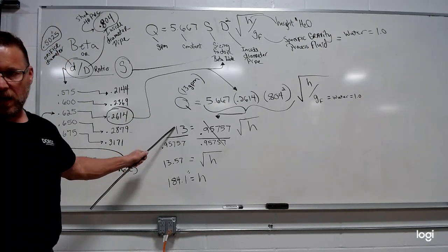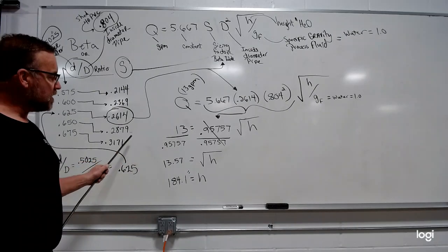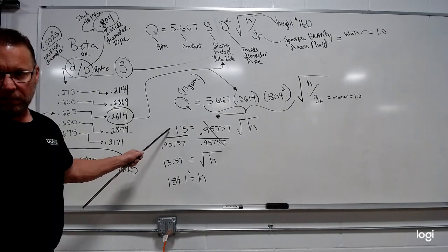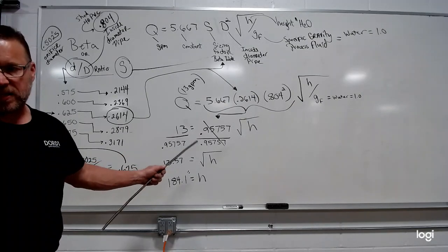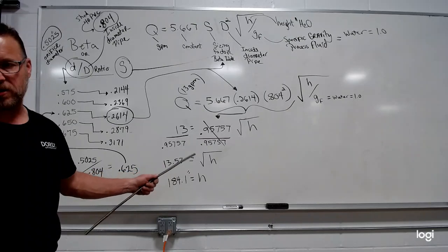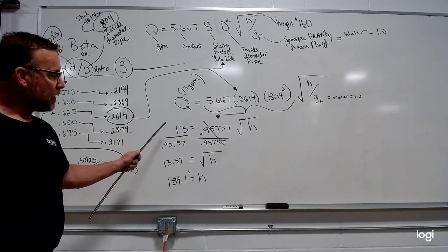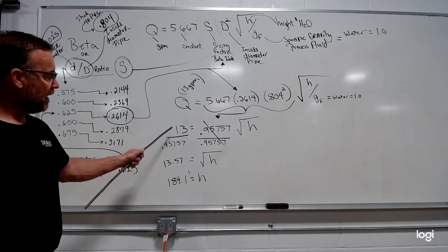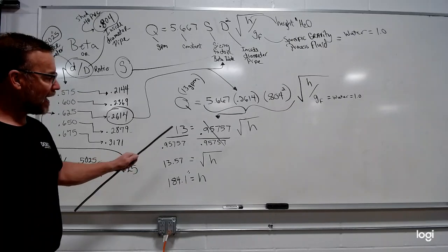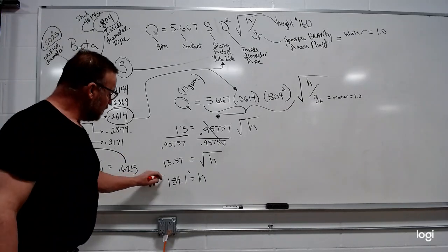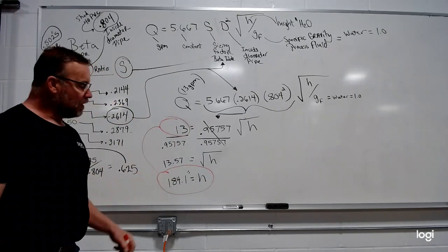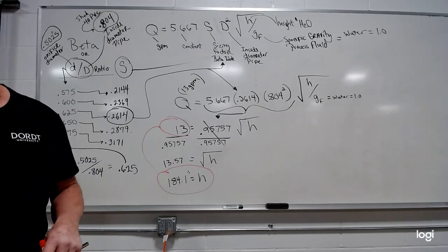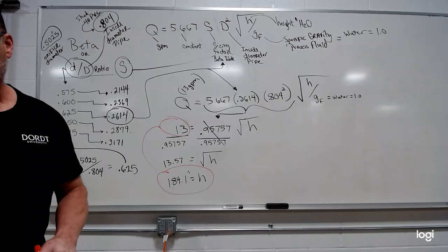I can go anywhere from 0 to 13 gallons per minute, and I can plug that number into this formula, and I can tell you what the pressure drop would be at 6 gallons a minute, or 3 gallons a minute, or 7 gallons a minute, okay? What we want to do, though, is find out what our pressure drop is at our maximum value, this 184 inches at 13 gallons per minute. These are what we have to put in our DP transmitter for our upper range value, our maximum pressure drop.